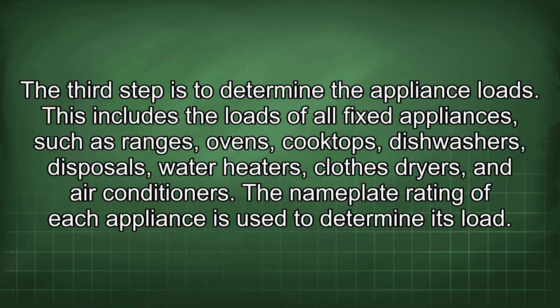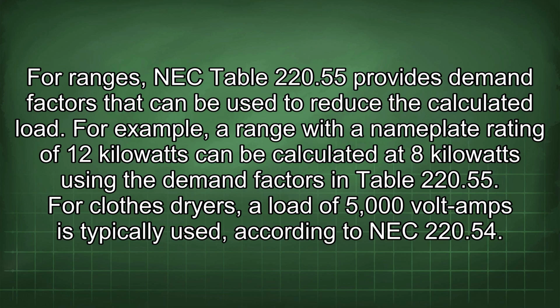The third step is to determine the appliance loads. This includes the loads of all fixed appliances, such as ranges, ovens, cooktops, dishwashers, disposals, water heaters, clothes dryers, and air conditioners. The nameplate rating of each appliance is used to determine its load. For ranges, NEC Table 220.55 provides demand factors that can be used to reduce the calculated load. For example, a range with a nameplate rating of 12 kilowatts can be calculated at 8 kilowatts using the demand factors in Table 220.55.